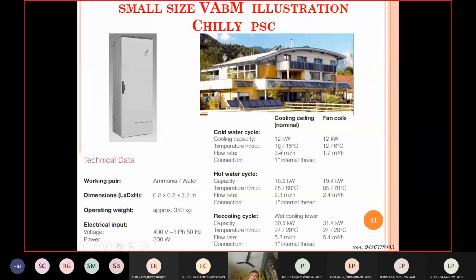So one important thing that I would like to draw your attention to is you can see here there are two applications of this unit shown. One is cooling ceiling, that is chilled ceiling or radiant cooling, and another is fan coils, the conventional unit, right? So if you want this much amount of cooling, what you see here is temperature in and out, right? So you need higher temperatures for the chilled ceiling type of application, while for the fan coils it is lower temperatures.